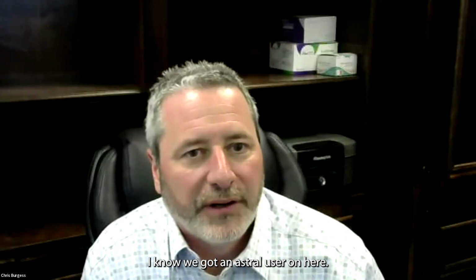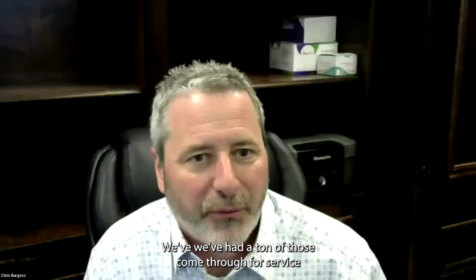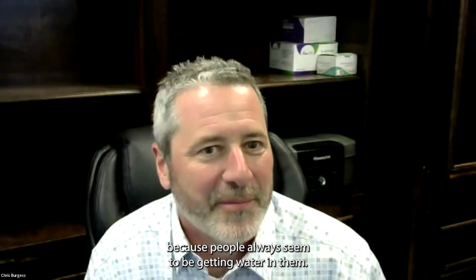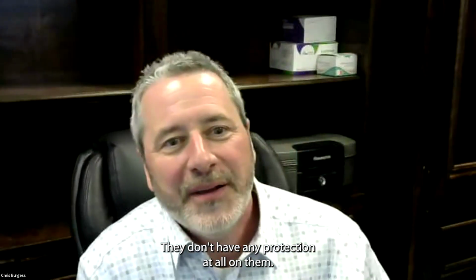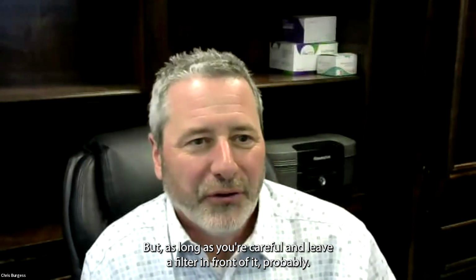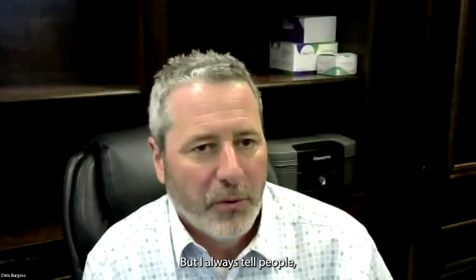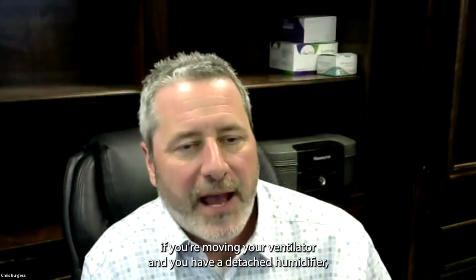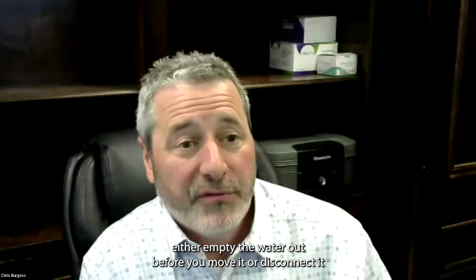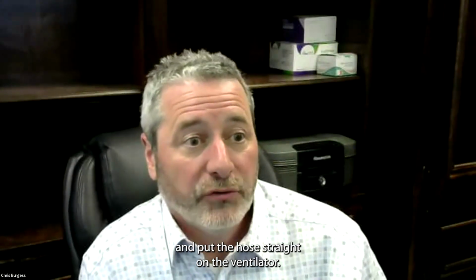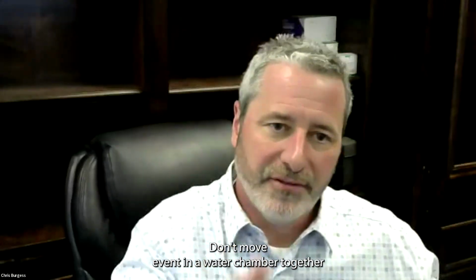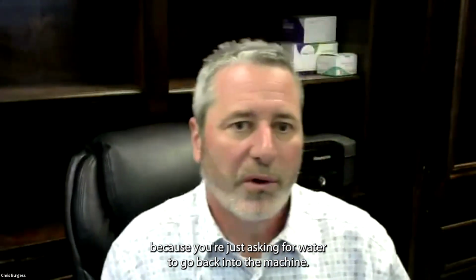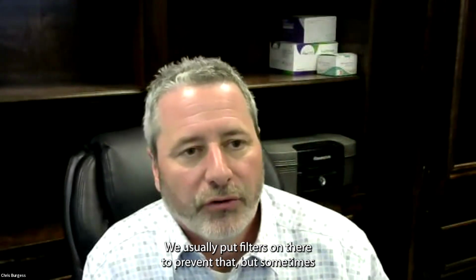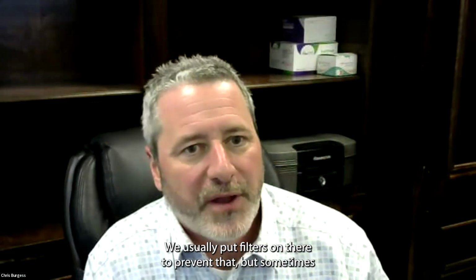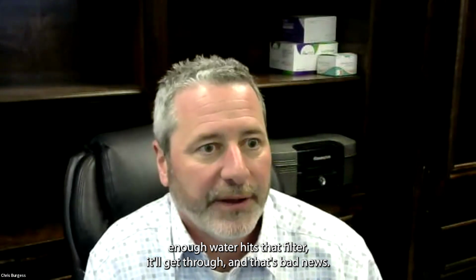I know we got an Astral user on here. We've had a ton of those come through for service because people always seem to be getting water in them. They don't have any protection at all on them. But as long as you're careful and leave a filter in front of it, probably okay. But I always tell people, if you're moving your ventilator and you have an attached humidifier, either empty the water out before you move it or disconnect it and put the hose straight on the ventilator. Don't move a vent and a water chamber together because you're just asking for water to go back into the machine. We usually put filters on there to prevent that, but sometimes enough water hits that filter, it'll get through, and that's bad news.